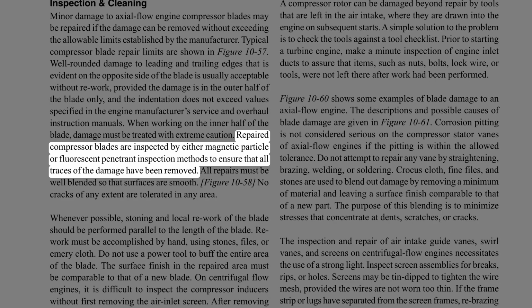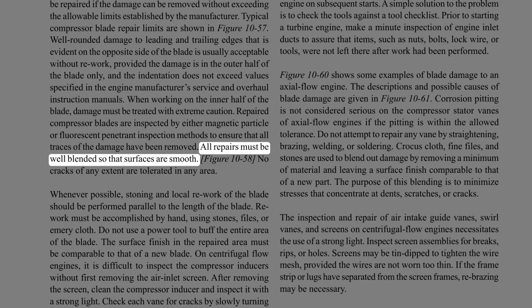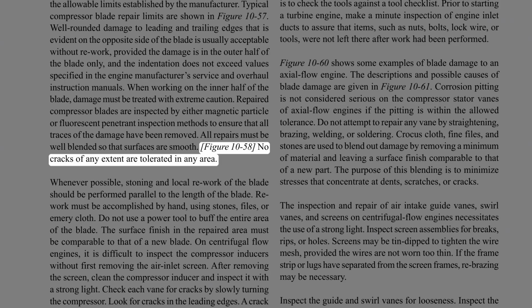Repaired compressor blades are inspected by either magnetic particle or fluorescent penetrant inspection methods to ensure that all traces of the damage have been removed. All repairs must be well blended so that surfaces are smooth. Figure 10-58. No cracks of any extent are tolerated in any area.